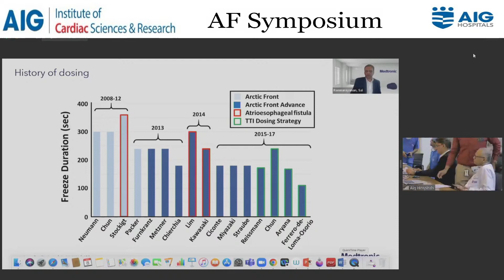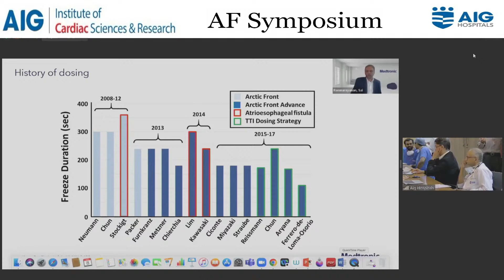So our first generation balloon required a 240-second freeze, which was the recommended, and people have done up to 300 or 400, and you can see that once you go above that 300 mark, you can have atrioesophageal fistula formation. And once the second generation came about, the ablation time significantly dropped to about 3 minutes on average, and people were going as low as 90 seconds in recent times. So there was a wide range of ablation strategies that people use. However, what should guide your ablation strategy should be the timed isolation.